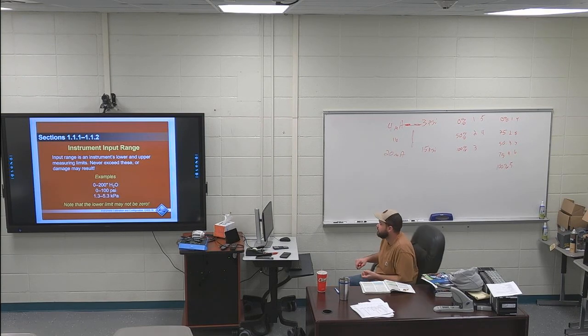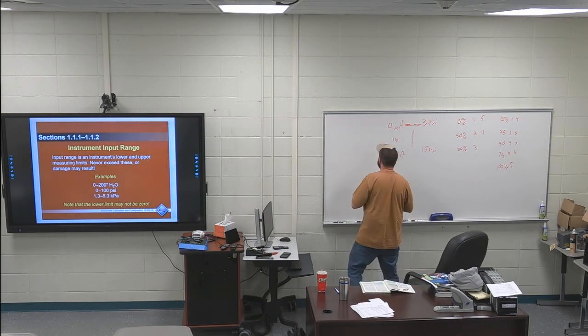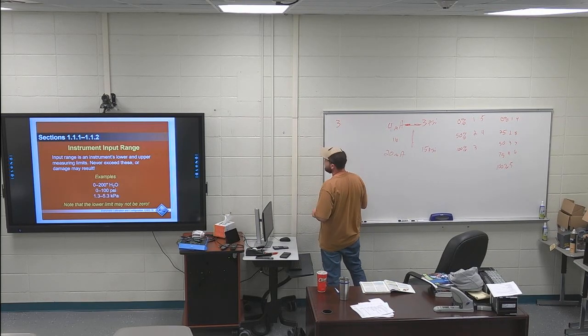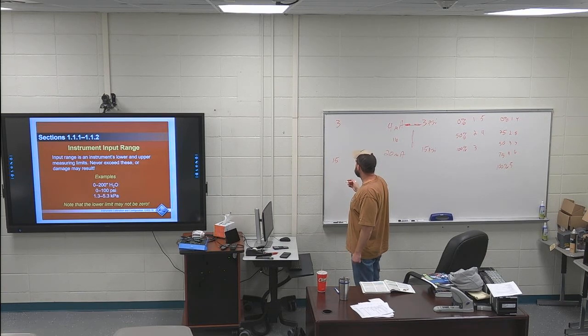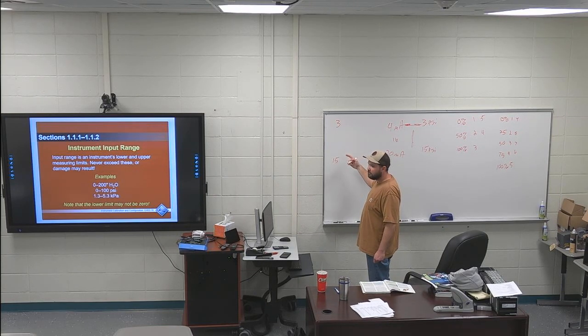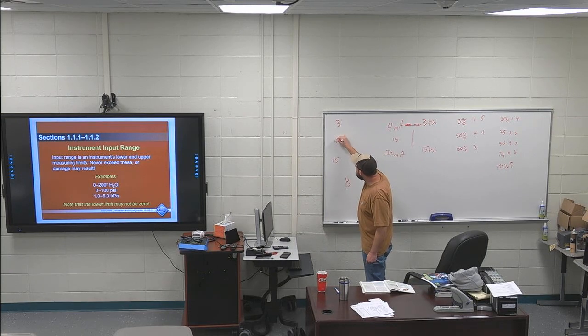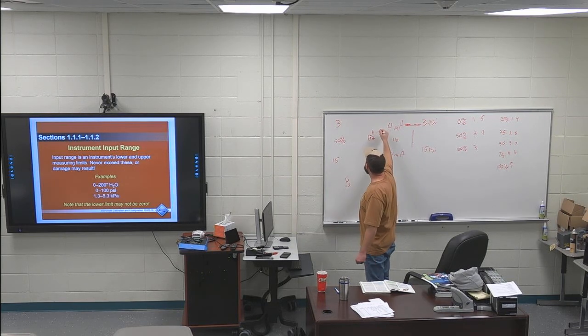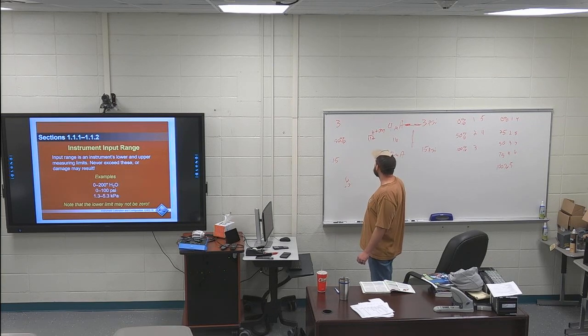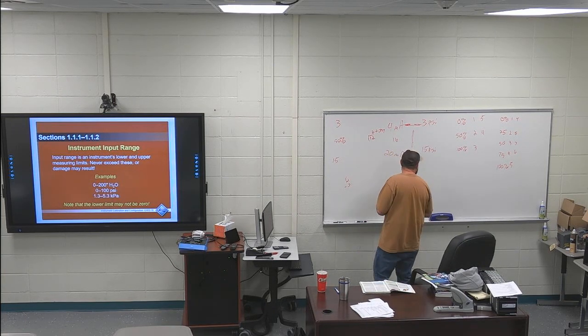It's doing it kind of weird, but say I had... I would just subtract the difference between both of them and divide that by 2, and that would be the middle one, right? Like 3 to 15: the difference is 12, divide by 2 is 6, plus 3 is 9, which is what they're doing. So to find my 50% point, you take that minus that, which gives you 12, divide that by 2, which gives you 6, and then you add your 3 to get 9. Yeah, I get it. I feel like I'm making it more confusing than it should be.